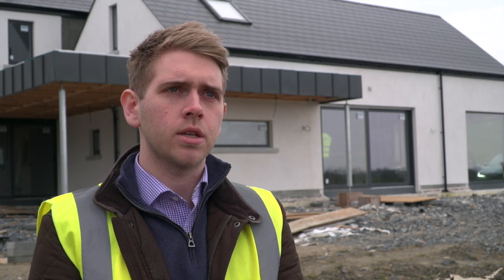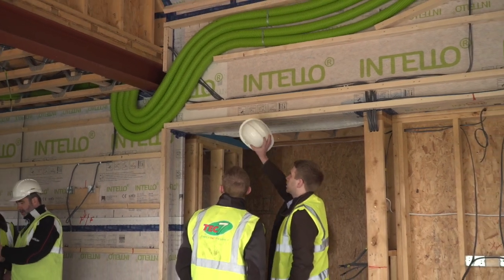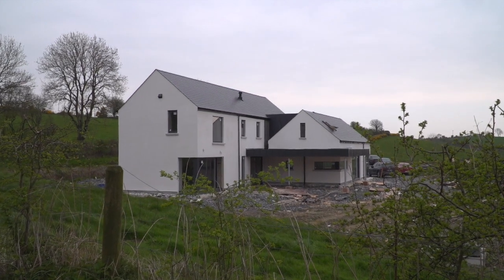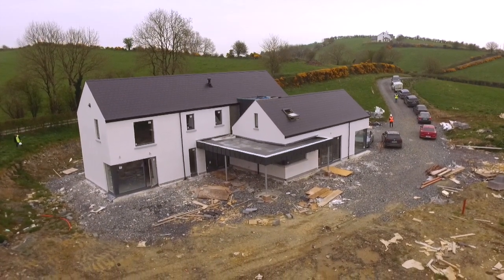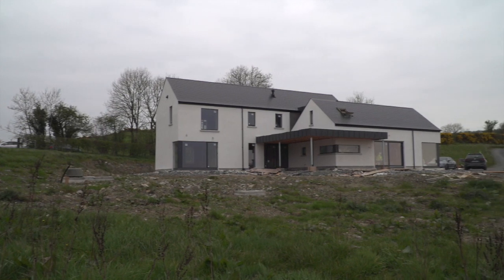The unit can ramp up for greater air changes — for example if somebody's in the shower, having a bath, or if there's a birthday party with more people in the house. The unit is bringing in fresh outside air through filters. Nile will be going for pollen filters and the F7 filter, which will filter out any pollen or pollutants in the air coming into the house. He can also upgrade to carbon filters, which will help filter any smells from nearby farms and silage in the area.